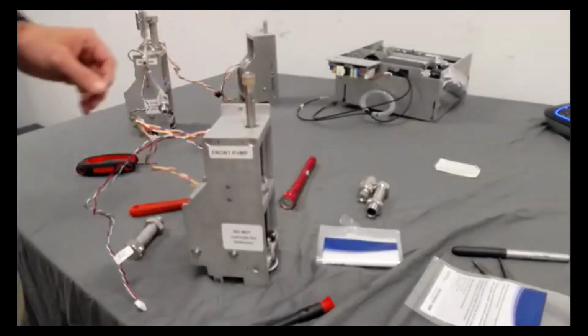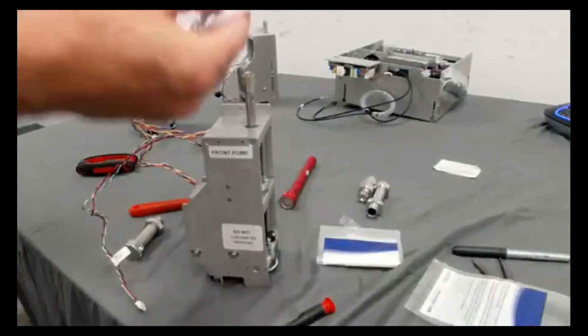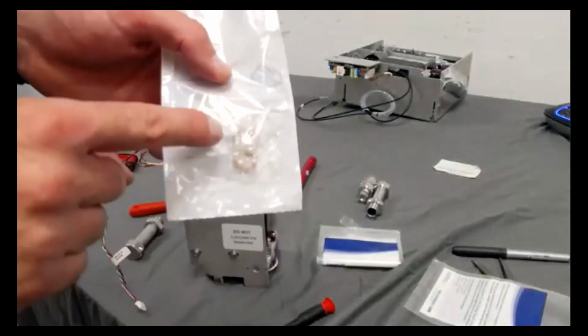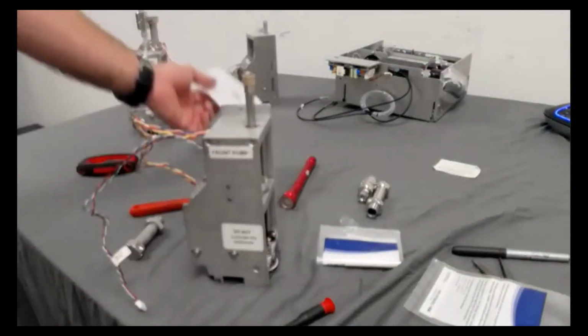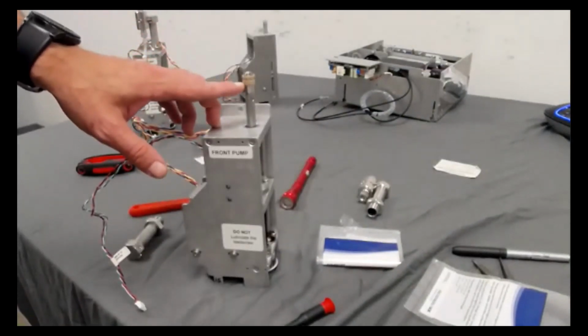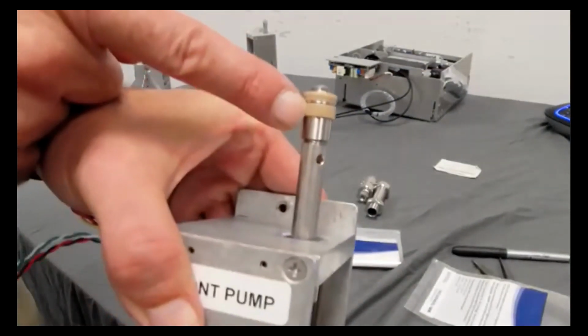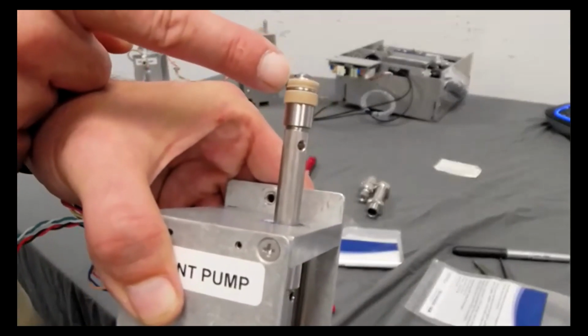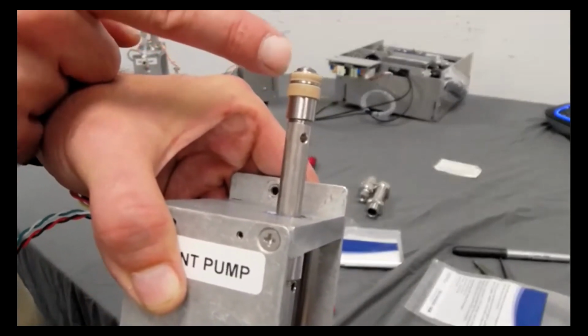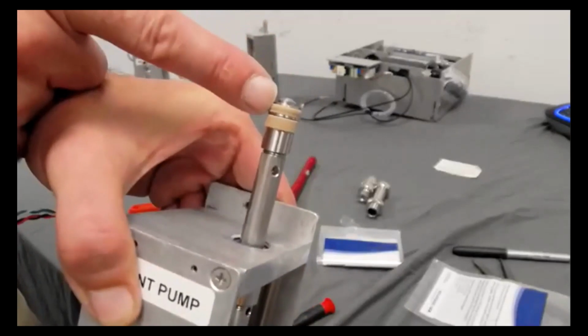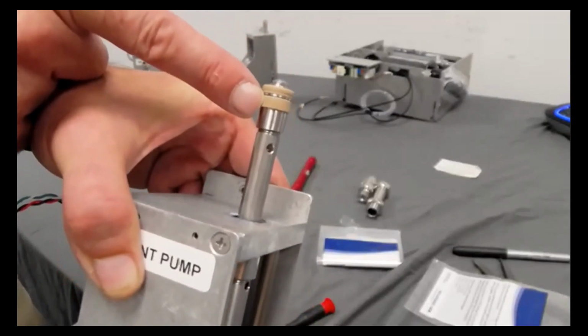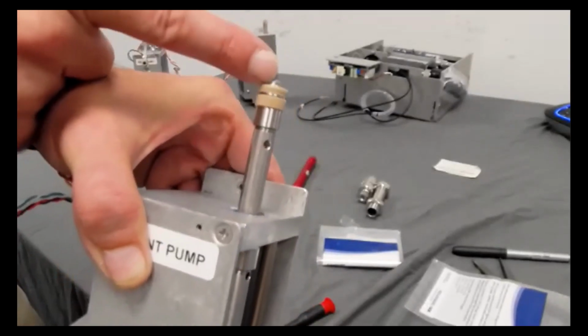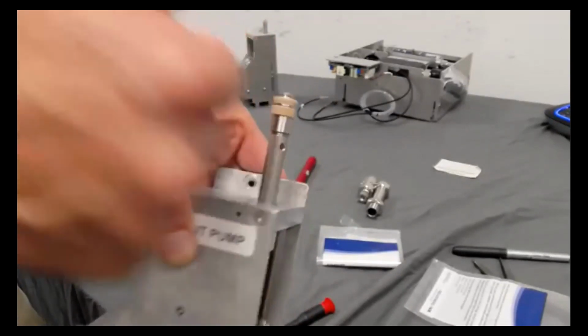So, come over here. My seals, there they are. So in here is going to be a new wear ring and seal. So the wear ring is the bottom part here. This is the wear ring. And this is the actual seal. Now, through the life of the seal it is going to wear down. If it wears down enough, the wear ring protects it in that it keeps the metal from rubbing on the metal. Make sense?